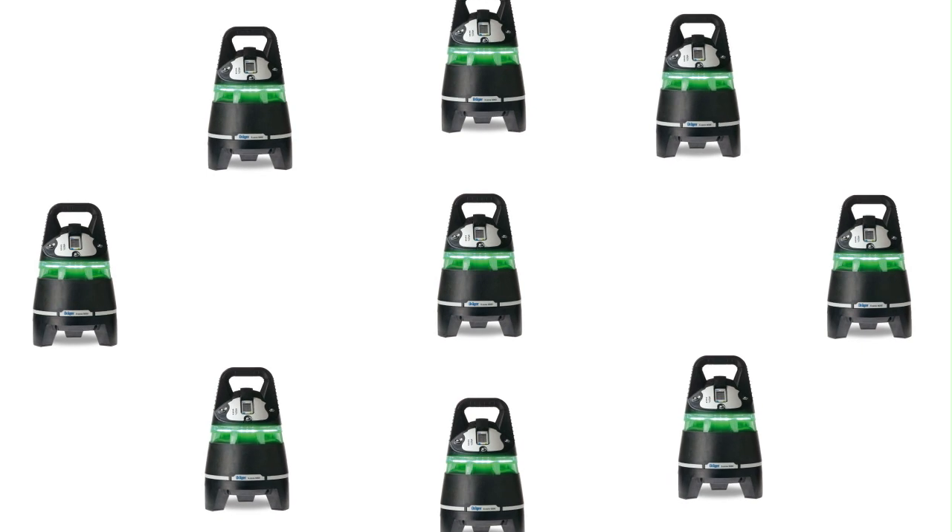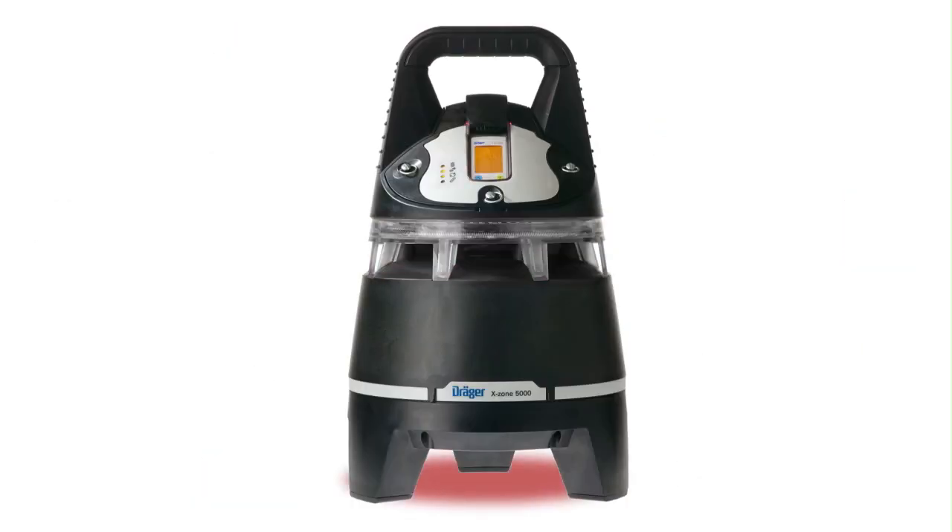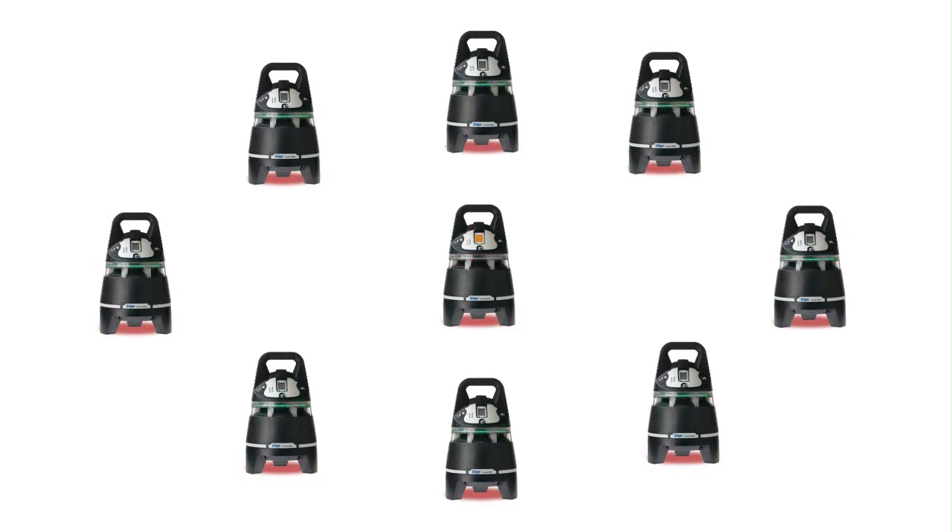A green LED shows that everything is fine. A red LED and a warning sound indicates that the device has detected an elevated gas concentration. It transmits the alarm to other surrounding devices. The LEDs of the other Dräger X-zone devices will then flash in red and green, indicating that an elevated gas concentration has been detected at another measuring device.